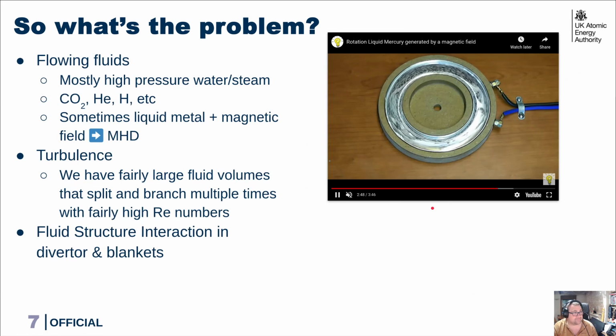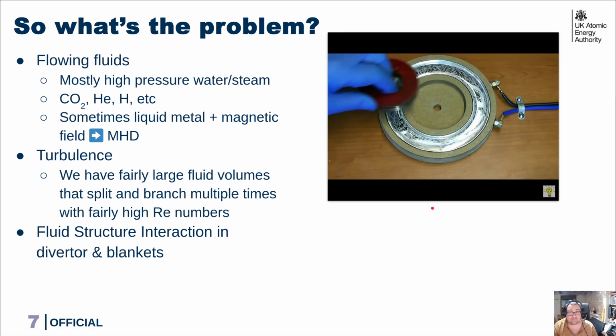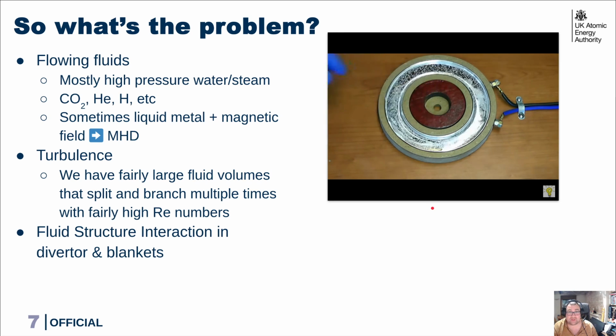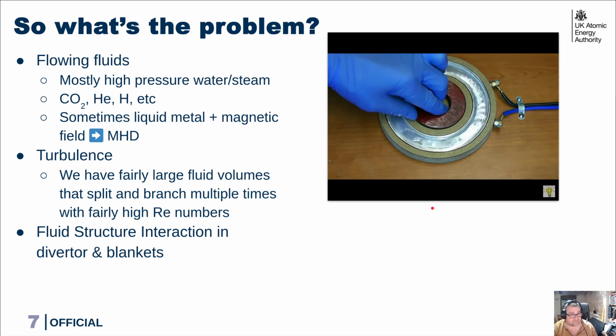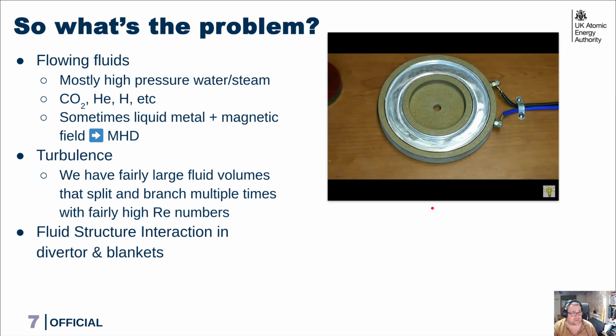We have a number of things we have to do. To compound matters, we obviously want to keep things cool. You don't want things melting. We therefore have to model the cooling fluids, which are typically high pressure steam or water, but sometimes this of course could be a gaseous coolant like CO2 or helium. However, sometimes we would like to employ liquid metal cooling, which is interesting for a number of reasons, but comes with an additional modelling challenge in that it's subject to magnetohydrodynamics, which increases the computational burden from just purely simulating a traditional fluid. We also have to worry about the electrical impact there too. And of course, you can also sometimes have turbulent flows, but not always, and that manifests itself as fluid structure interaction in the blankets.